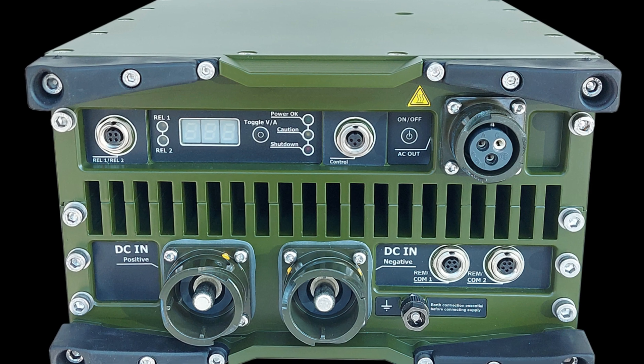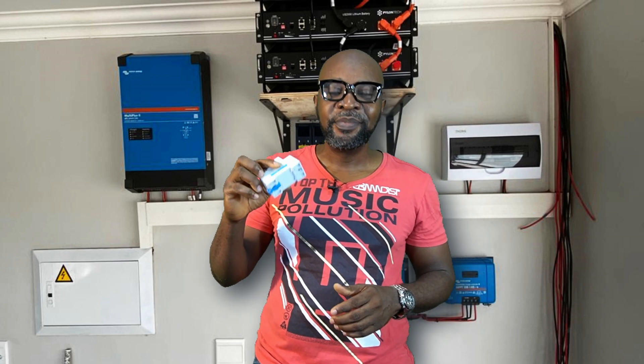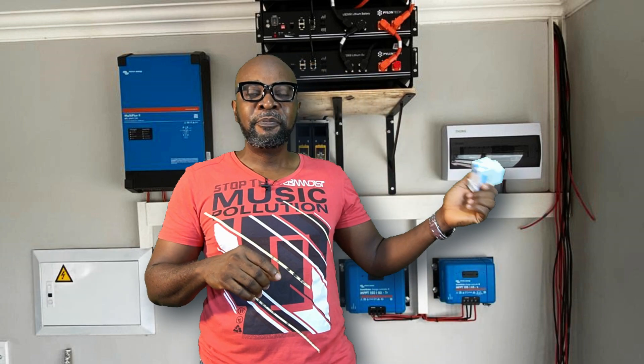Now let's bring it back to your solar system installations. This here is a digital surge protector — really very cool. It is connected to your inverter: line-in connected from the input and line-out connected from the output. You need to protect both the input and output because the inverters are expensive — that's someone's money. As a homeowner, you need to ask your installer repeatedly: did you include an SPD? It's important. If there's a surge, it doesn't get to the inverter and destroy it.